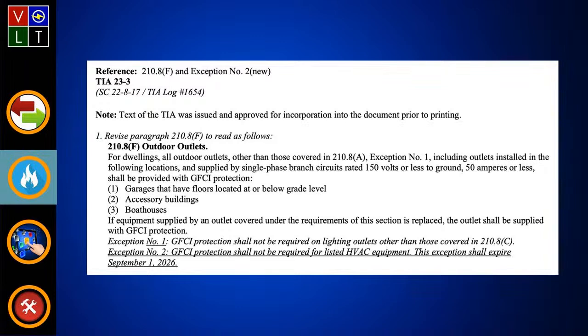And that could be like in some of those mini split systems, it could connect to an outlet, and there could be multiple things that require GFCI protection. You could have two sides of that split system that requires GFCI protection, in my opinion. But at the same time, that's really confusing, and I will read and argue with an inspector.